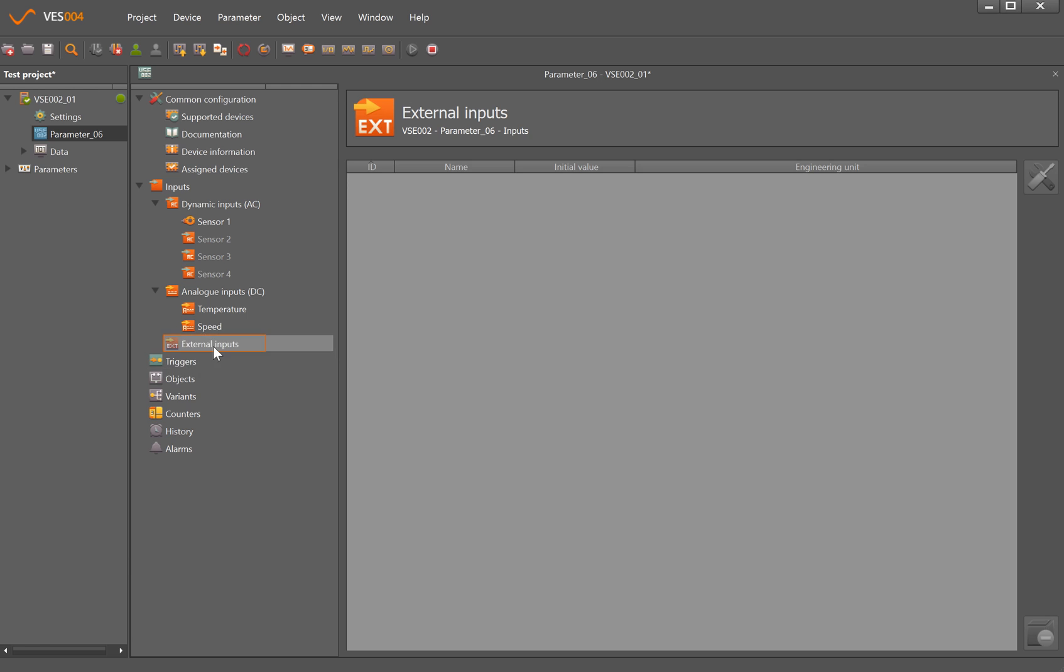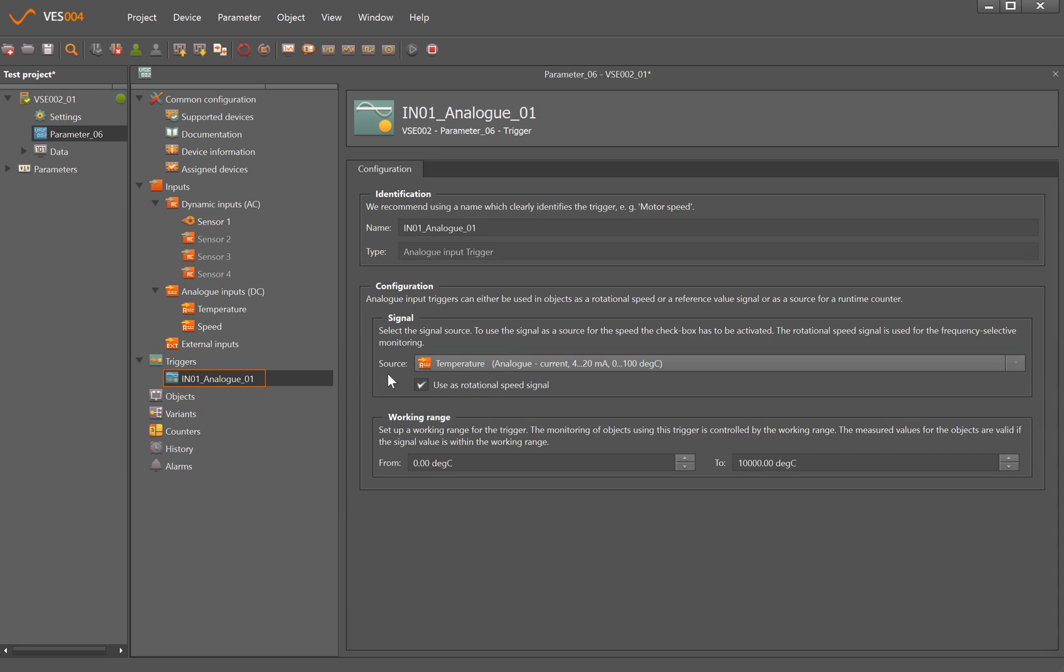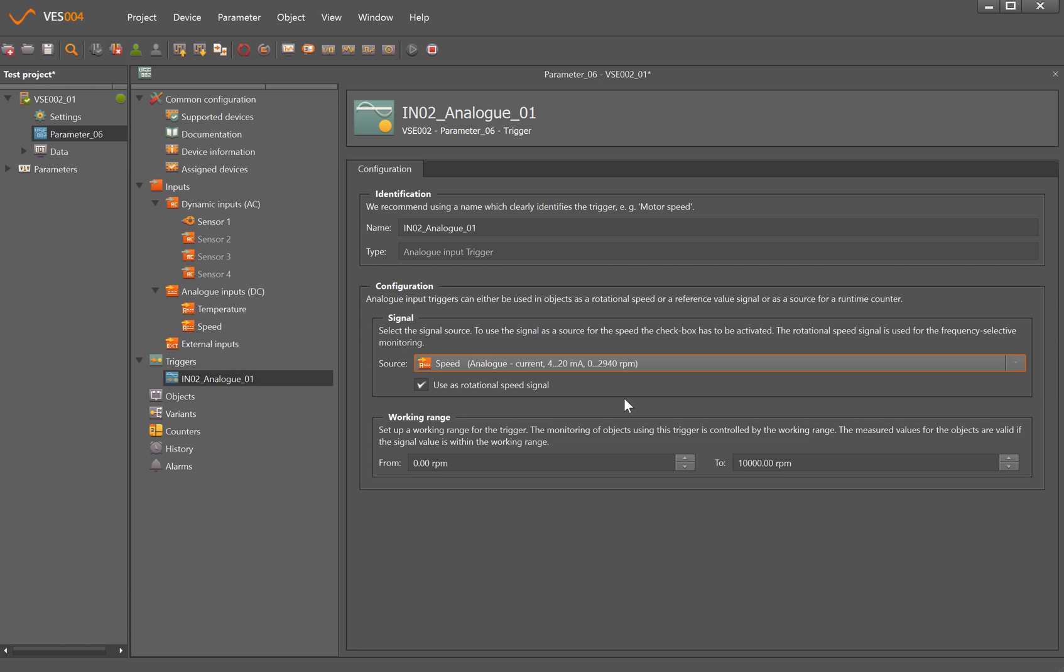So the next thing we have to set up is triggers. So when we come to setting up the objects, for instance unbalance and looking for bearing defects, we need to tell it what trigger these relate to. So new trigger - we're going to set up based on an analog input. Now the analog input is not temperature because we want these to be based on the speed. And this means as the speed changes, anything that's related to here that's looking for individual frequencies related to the speed of the machine will track up and down the frequency spectrum as the speed of the machine changes.